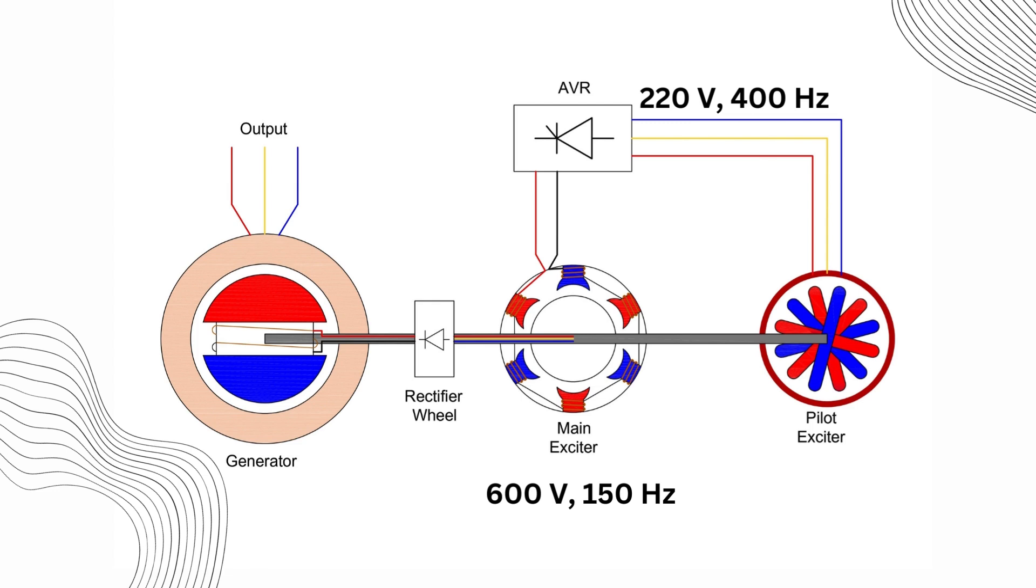The AVR is key in controlling this process. When the power from the pilot exciter reaches the AVR, it's compared to a set point voltage against the main generator's output voltage. The AVR then determines how much voltage should be sent to the main exciter. The higher the field winding voltage in the main exciter, the higher the armature current. This current is rectified again in the diode rectifier wheel before it reaches the rotor winding.